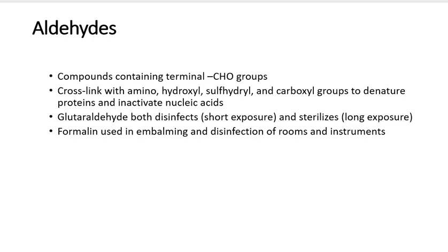The one thing with glutaraldehyde is that you don't have to change it every single time, but you do need to change it frequently. I've seen some docs that do not change this glutaraldehyde frequently enough, and you can get infections from it. So if you work in an office where you are using glutaraldehyde, make sure they change it if they have these kinds of instruments that they have to disinfect so they can use them. All right.